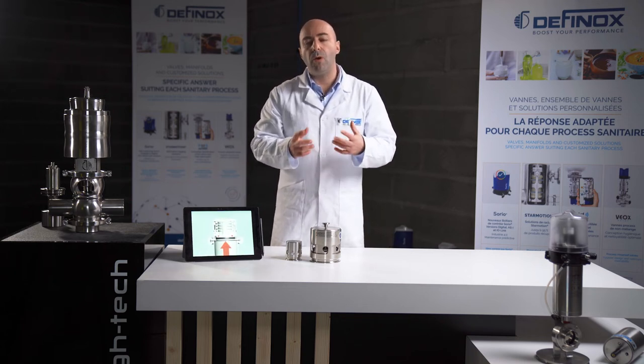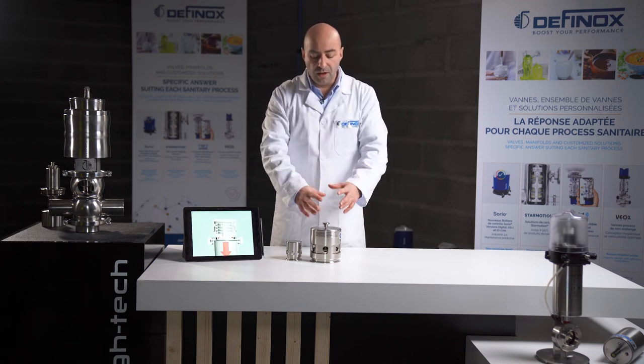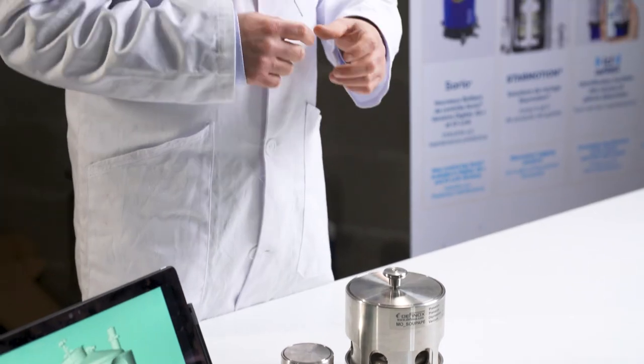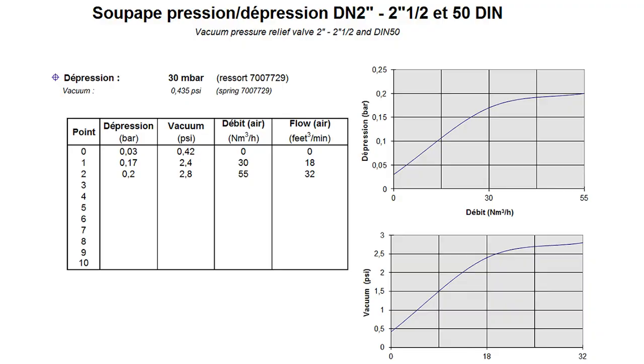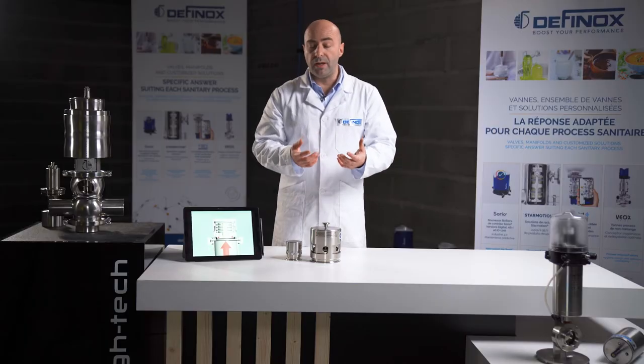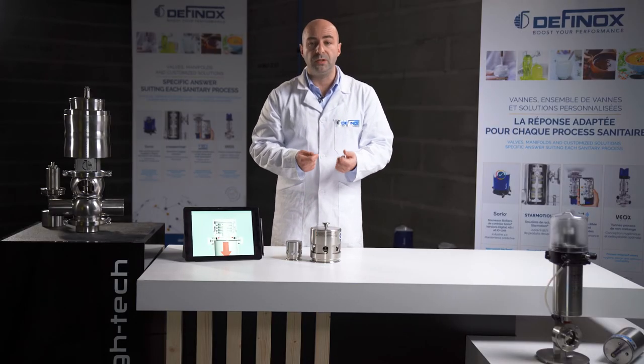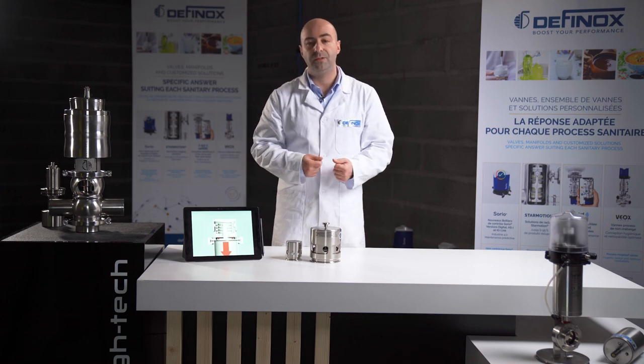Now the question you may have is: how do I select the best design or preset to protect my tank? On the Definox website, you will find a chart with two parameters: what will be the flow to exhaust, and what is the maximum pressure I would like to reach in my tank. Based on these two data points, it will give you the housing size and the spring to select. It's quite an easy process, but for any question or doubt about the selection process, we are here to assist you.